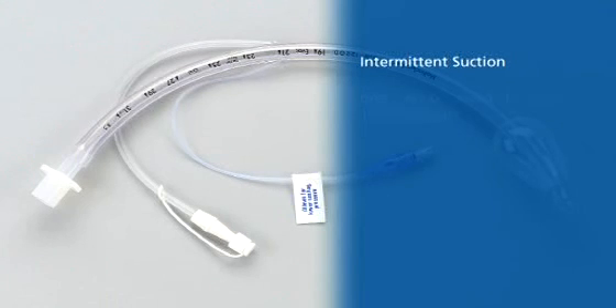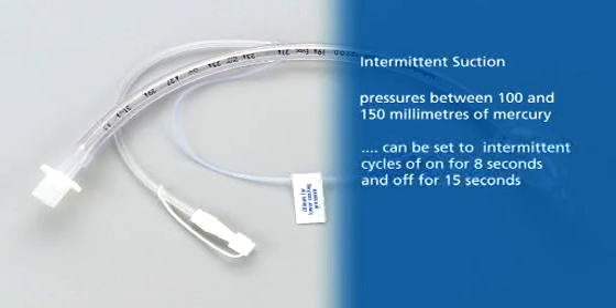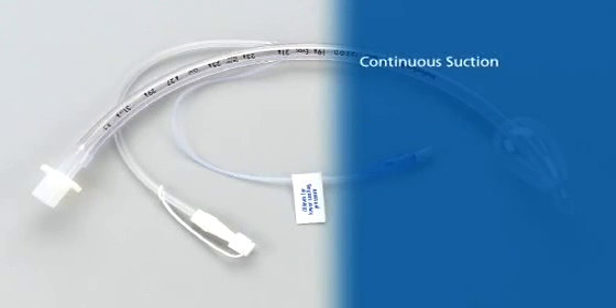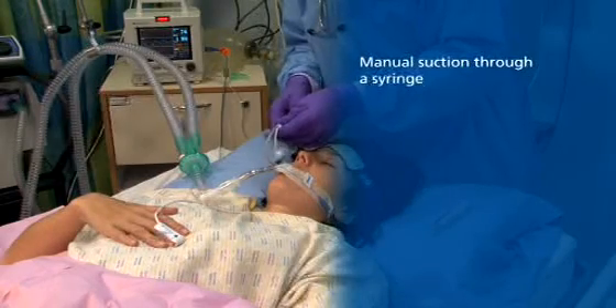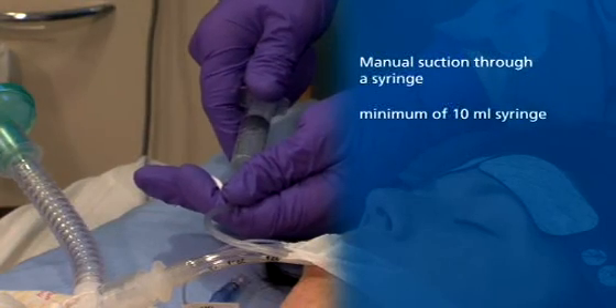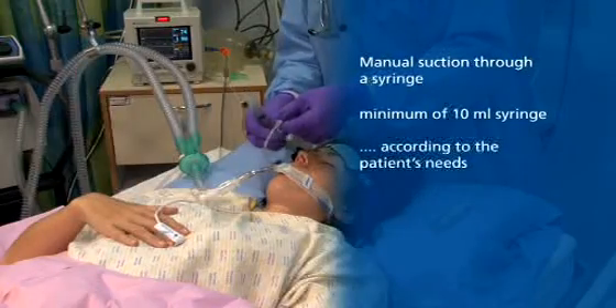Intermittent suctioning can be applied using pressures between 100 and 150 mmHg and can be set to intermittent cycles of on for 8 seconds, off for 15 seconds. Continuous suctioning can be applied with pressures not exceeding 20 mmHg. Please see the instructions for use for further guidance. Manual suction can be facilitated using a minimum of a 10 ml syringe and should be applied only in accordance with the patient's clinical needs.